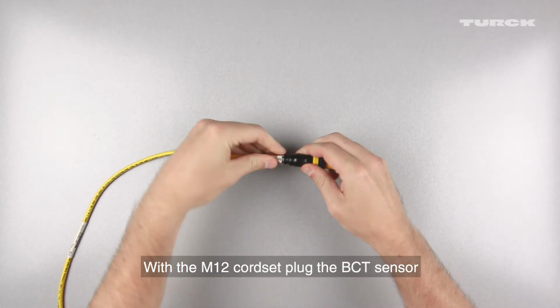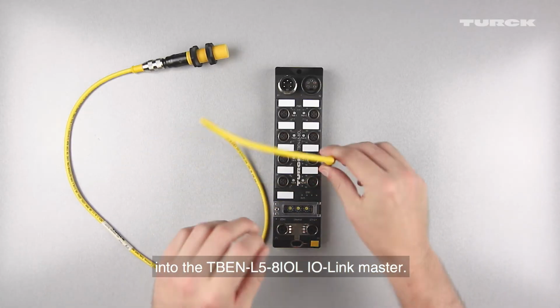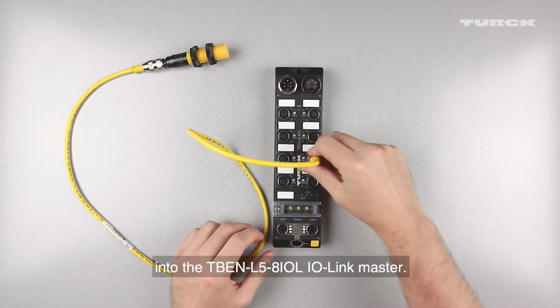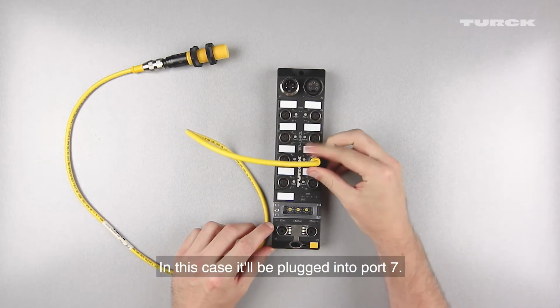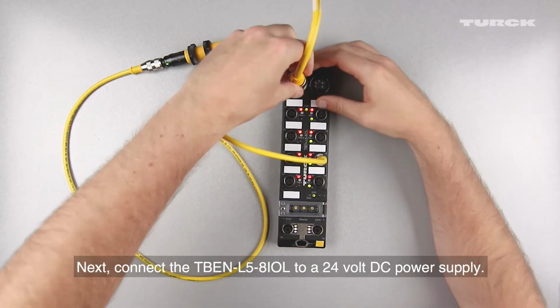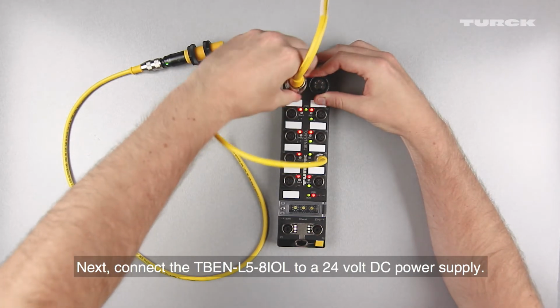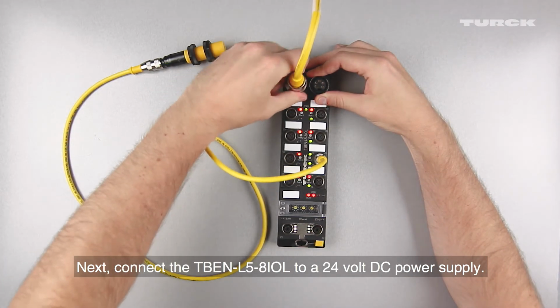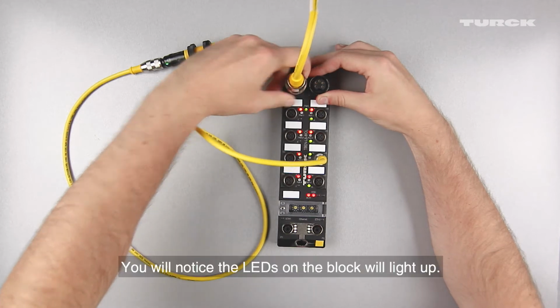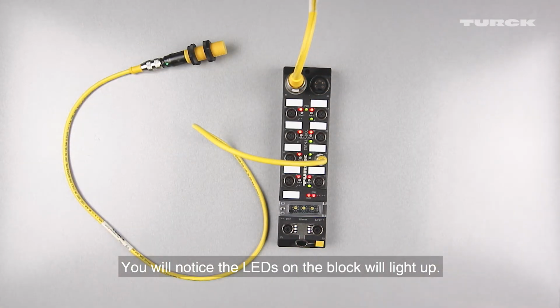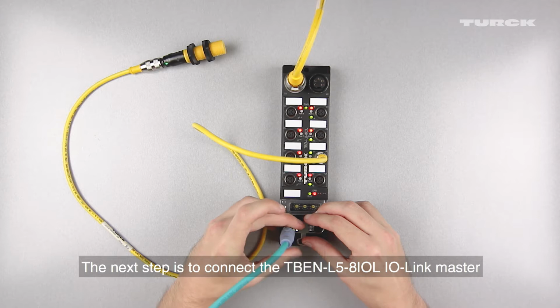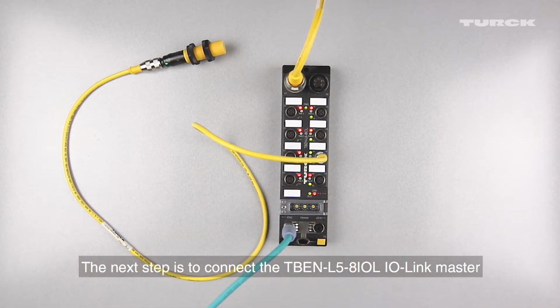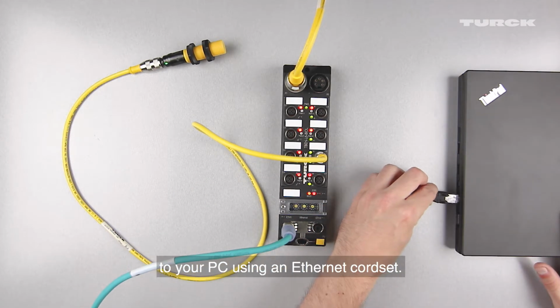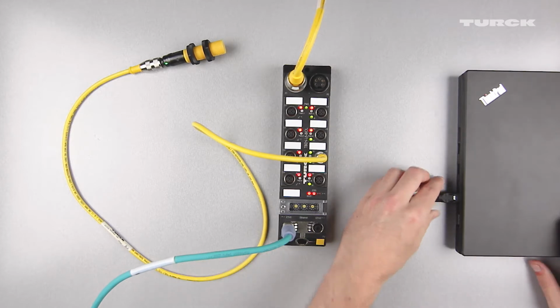With the M12 cord set, plug the BCT sensor into the TBEN-L5-8IOL IO-Link master. In this case, it will be plugged into port 7. Next, connect the TBEN-L5-8IOL to a 24-volt DC power supply. You will notice the LEDs on the block will light up. The next step is to connect the TBEN-L5-8IOL IO-Link master to your PC using an Ethernet cord set.